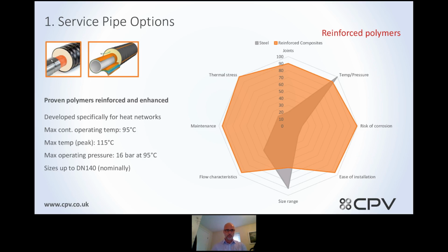These are coiled systems, again, so typically on drums. They will do 16 bar at 95 degrees C. They will take peaks of 115 degrees C, but that affects the service life. So how this benefits over the rigid polymers, you're reducing your amount of joints. You've obviously still no risk of corrosion. The size range on this is typically up to DN140, that's the service pipe bore size. That's typically 160 millimetre OD.